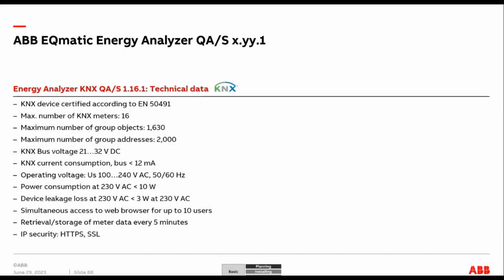If we look at the technical data for the device, it's certified according to EN 50491, which of course is the KNX standard. We can connect up to 16 meters. We can have a maximum number of group objects of 1630. Now that's quite a lot for any of you that do a bit of KNX programming, you know there's a whole lot of work gone into that one. With a maximum number of group addresses of 2000. So it really is quite a big device that can handle a lot of work.